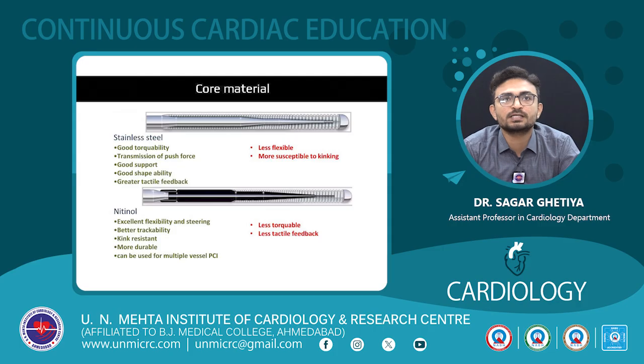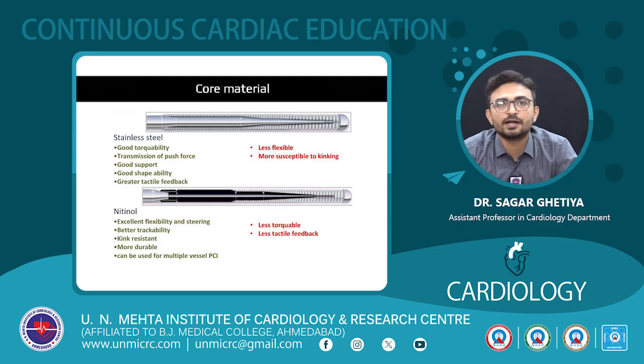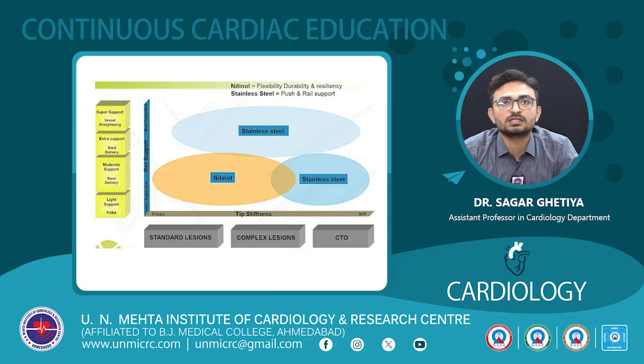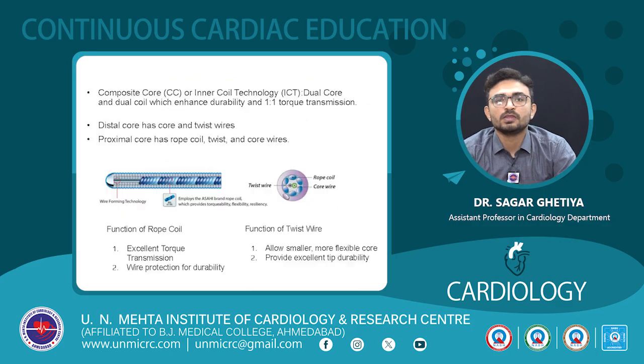Nitinol has the advantage of flexibility, kink resistance and being more durable, but it is less torqueable and gives less tactile feedback. So nitinol core is used in workhorse wires for standard lesions, while for complex lesions and CTO that require good support, stainless steel is more used.